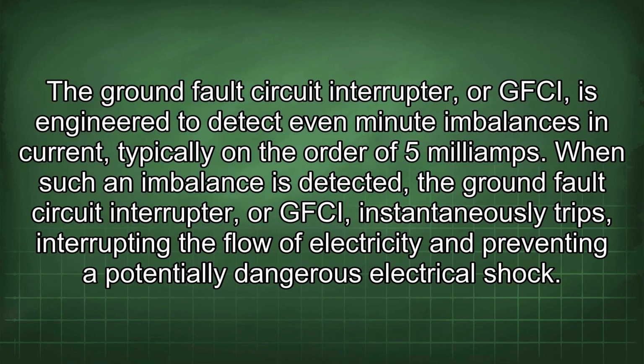The GFCI is engineered to detect even minute imbalances in current, typically on the order of 5 mA. When such an imbalance is detected, the GFCI instantaneously trips, interrupting the flow of electricity and preventing a potentially dangerous electrical shock.